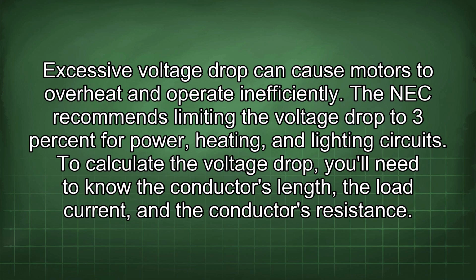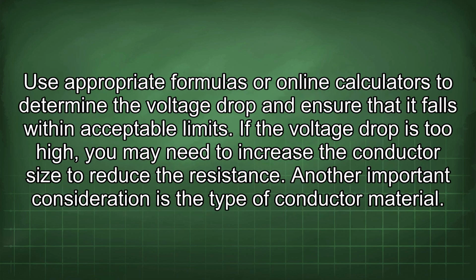To calculate the voltage drop, you'll need to know the conductor's length, the load current, and the conductor's resistance. Use appropriate formulas or online calculators to determine the voltage drop and ensure that it falls within acceptable limits. If the voltage drop is too high, you may need to increase the conductor size to reduce the resistance.